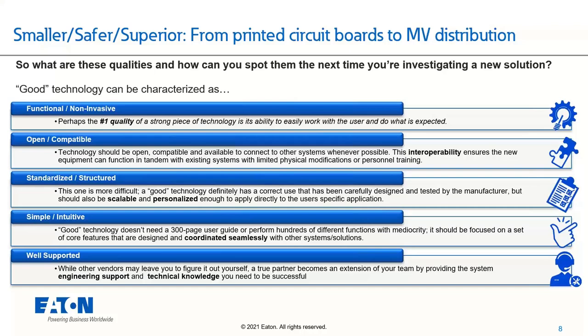The second one to mention is open or compatibility. From a software sense, a lot of folks might think like open source or intercommunicable. So you might have multiple protection relays on a site, and you might want to have the same type of relay all over your site so you have that compatibility. And that does not necessarily mean that it's exclusive to single relay to single relay. You don't necessarily have to have the brand, but if you were designing something that used DNP3 protocol to communicate, you might want to make sure that your other equipment is also compatible in that avenue, to make sure, again, that the use case is optimized and as repeatable as possible.